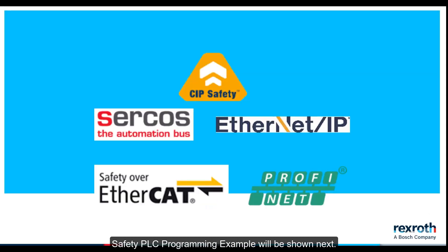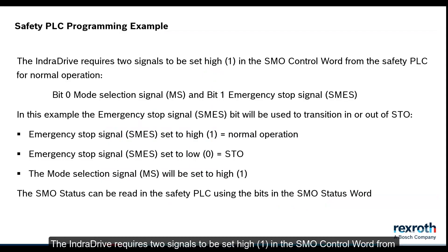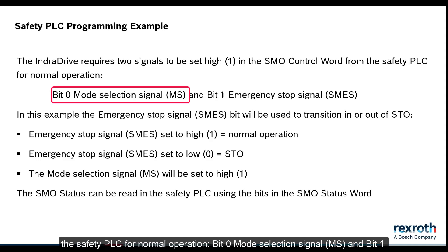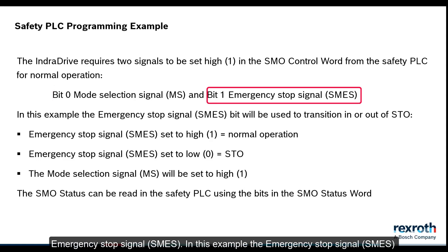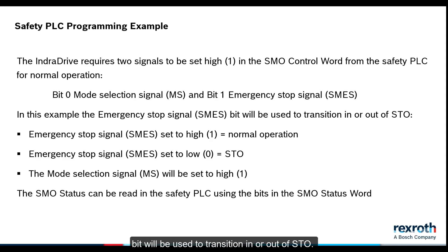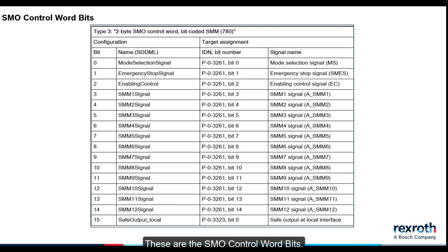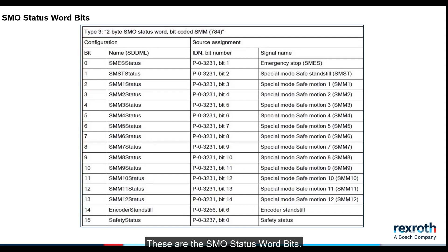A safety PLC programming example will be shown next. The IndraDrive requires two signals to be set high in the SMO control word from the safety PLC for normal operation: Bit 0, Mode Selection Signal MS, and Bit 1, Emergency Stop Signal SMES. In this example the Emergency Stop Signal SMES bit will be used to transition in or out of STO. These are the SMO control word bits. These are the SMO status word bits.